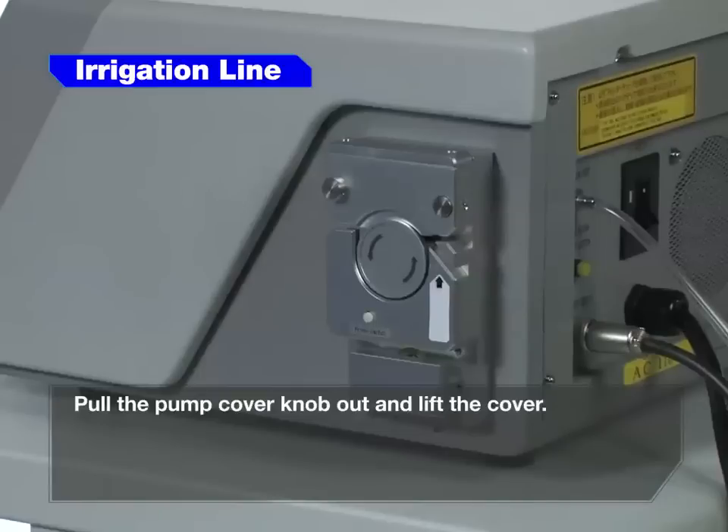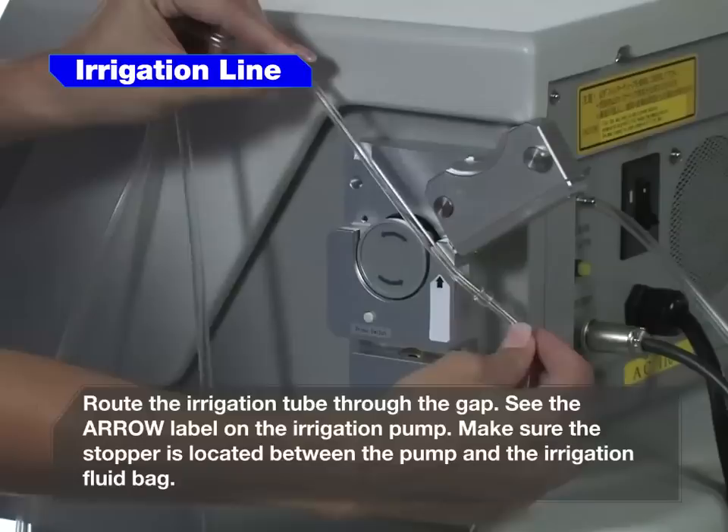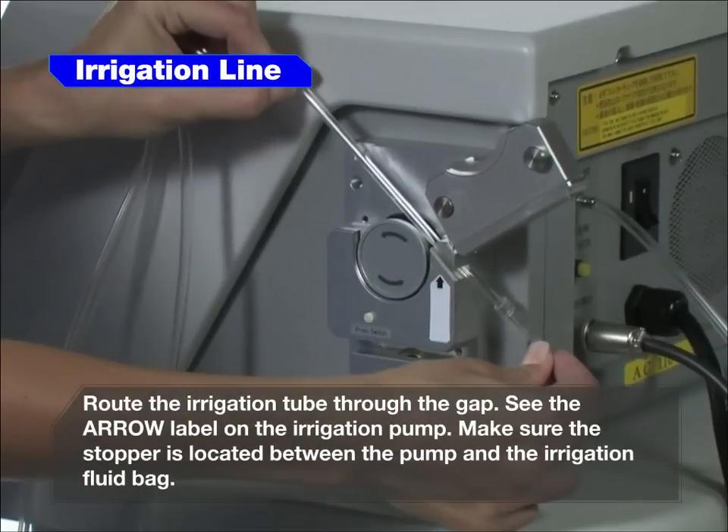Pull the pump cover knob out and lift the cover. Route the irrigation tube through the gap. See the arrow label on the irrigation pump. Make sure the stopper is located between the pump and the irrigation fluid bag.